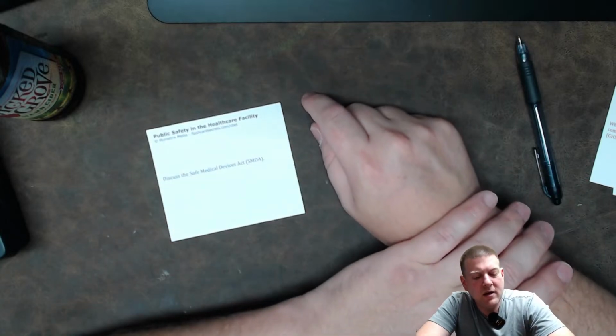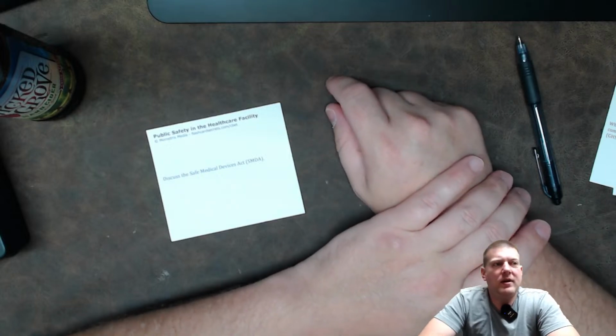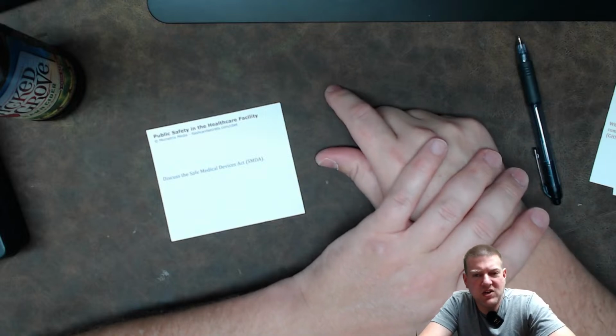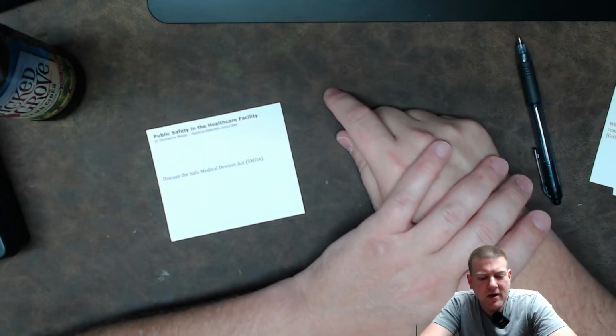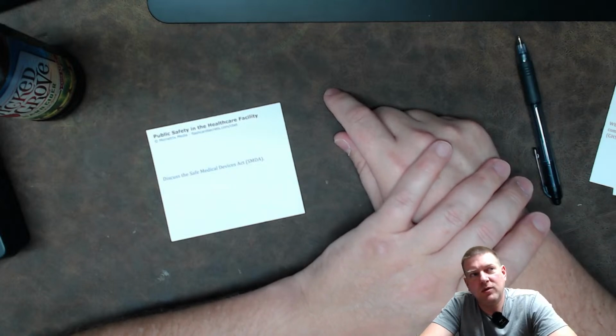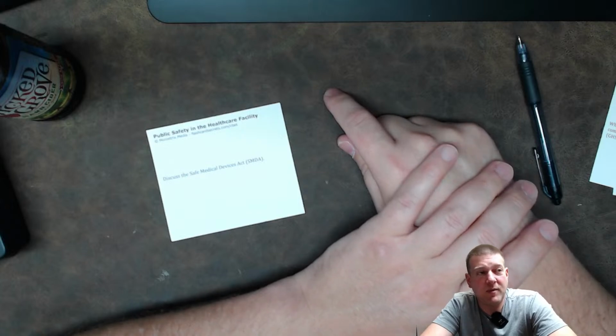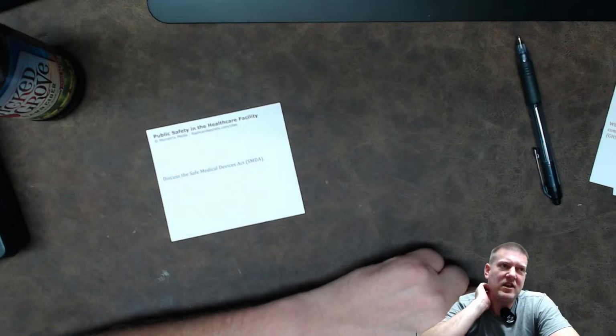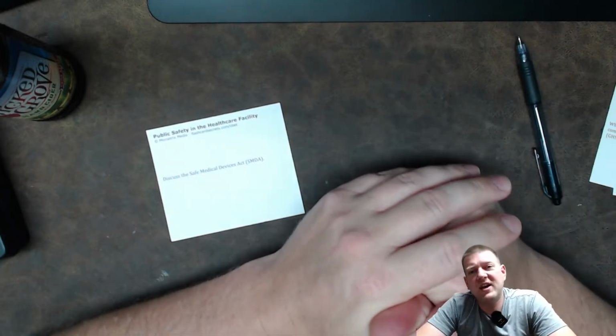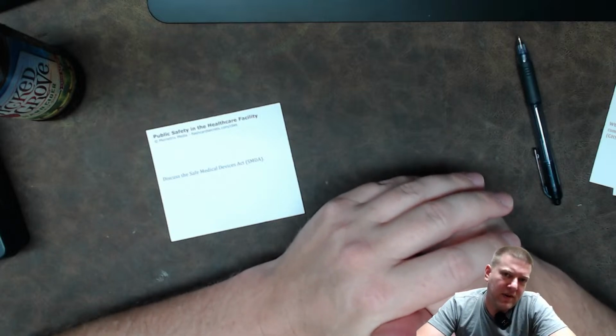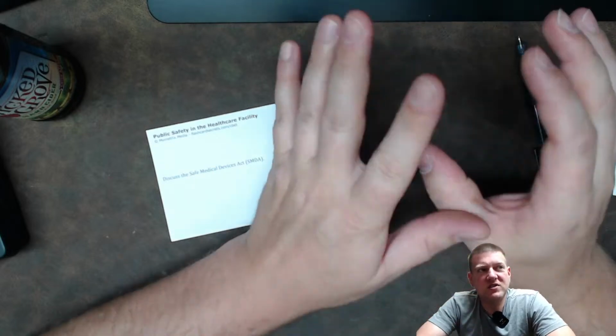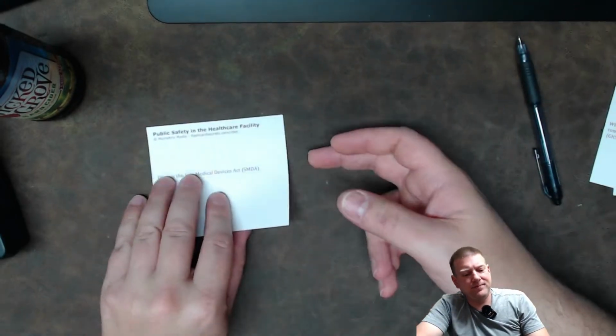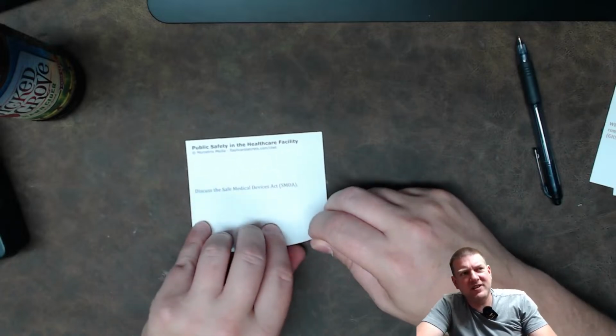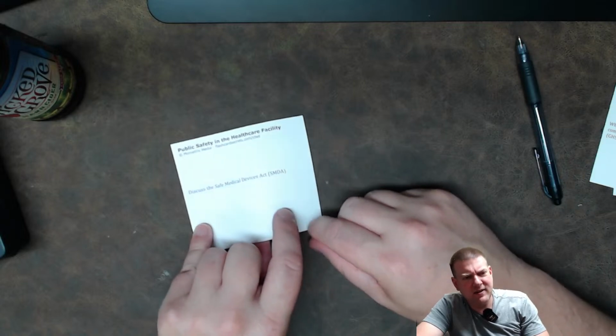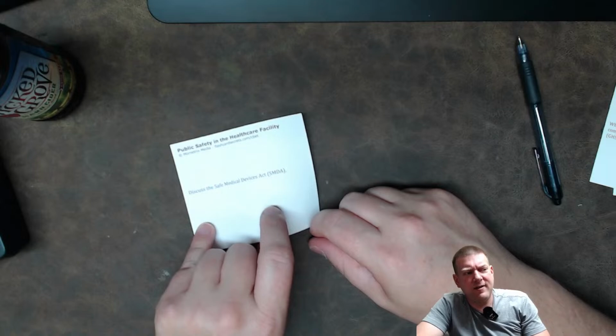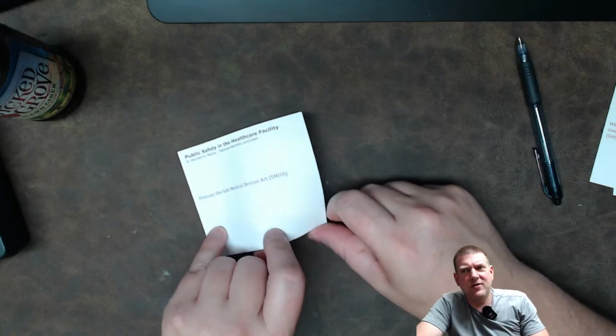So the Safe Medical Devices Act: it's everybody's responsibility who's around medical equipment when a patient incident is involved, especially when a patient is injured. You're required to relay that information both to the FDA and to the medical equipment manufacturer. That's why whenever you call a manufacturer and say you have to return a device for repair, they always ask you those generic questions like, was a patient involved? Was there a delay in patient care? Those questions are because of the Safe Medical Device Act. Now, I thought the Safe Medical Device Act also required certain devices to be tracked, like defibrillators. I thought for sure it was the SMDA that required those items to be tracked.